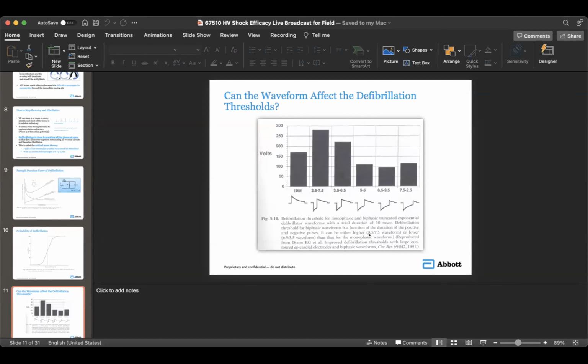So Doctor, that means we should be counseling the policymakers and administrators when they are purchasing those machines. They should contact the end users and the specialists, for example, to get the machine with biphasic, sync mode, and the pacing modes. So this is the best defibrillator. It has the pacing mode, it is biphasic, and it is synchronized. But sometimes you see the policymakers and the administrators just go and get a contractor and bring monophasic, no pacing mode in it. And you have to work with what you see in the hospital, and it doesn't all go well. So I think we have work to do to convince them. Always consult the specialist. Yes, I agree with you.